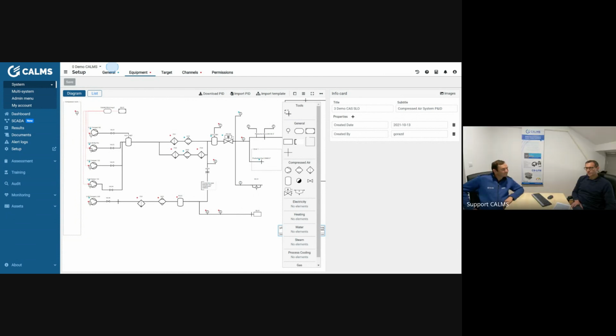Yes, sir. I think that with the measurements, I will be able to prove what's going on in your system. So I will actually measure all your compressors. This is the schematic that we have drawn during the visit when I entered your plant. And what I see here is that you have 4 compressors, and you bought a new one because you had this problem, obviously, and you connected this through a special line to the common receiver. Yes, that is correct.